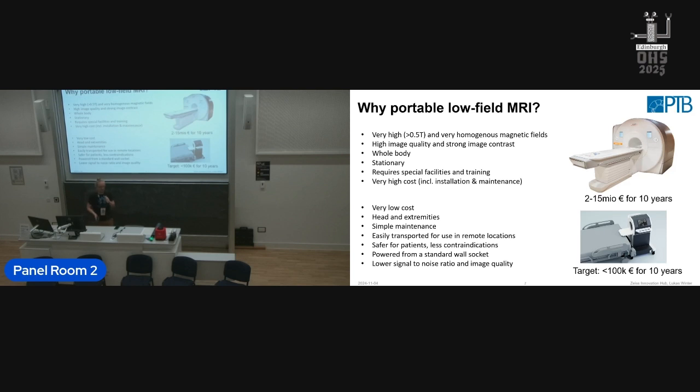And I think the map that Scott has shown, this is also true for MRI. There are many regions which are completely uninvented yet with this technology. And then we have our very low cost machines, or our low field devices, which you can see here. We have a target cost of below 100K over these 10 years. 10 years is a typical time such a machine is in operation. And 100K is not the material cost, but something we believe can be done also as a market price, or basically a cost for a hospital. So that's where we want to get to.